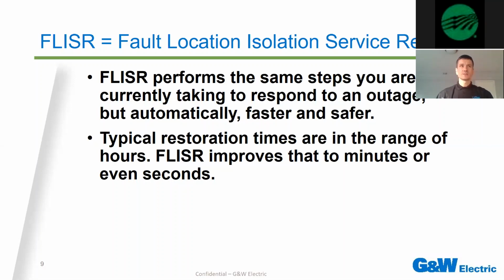One of the fun acronyms in the industry is FLISR, which stands for Fault, Location, Isolation, and Service Restoration. That sounds like a lot, but it's essentially everything you already do manually, done in an automated, faster, and safer way. If you have a fault in the system, you need to be notified, either by customers calling in or some kind of fault indication. Then you need to locate the fault—that's fault location. Then you typically send a crew out to isolate the fault so it can be worked on or repaired, true for overhead lines as well as underground faults.